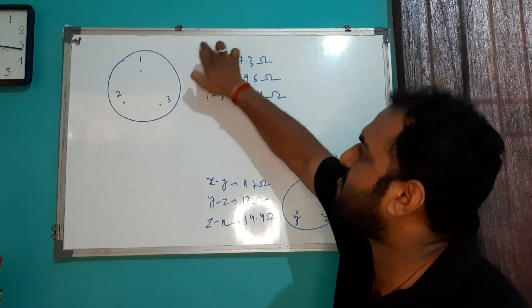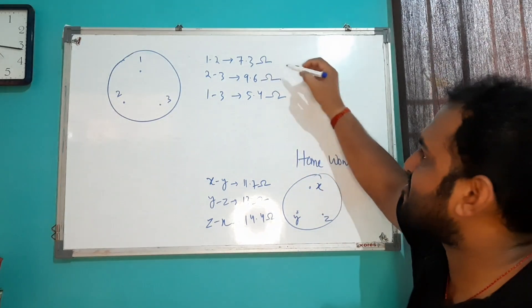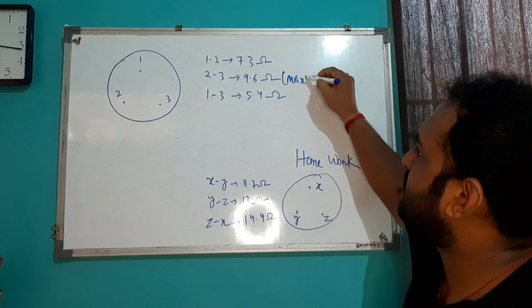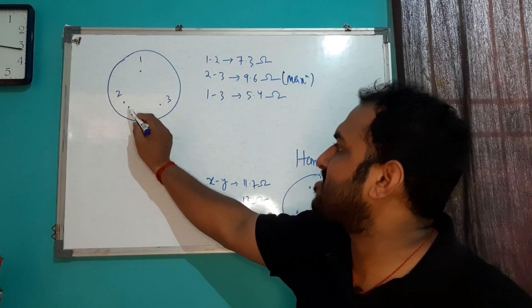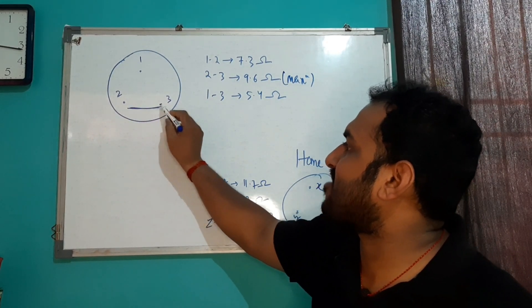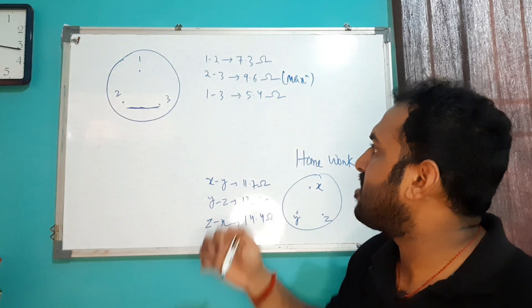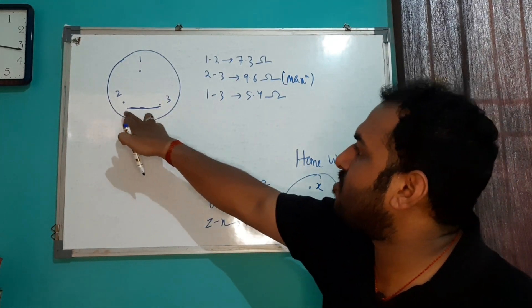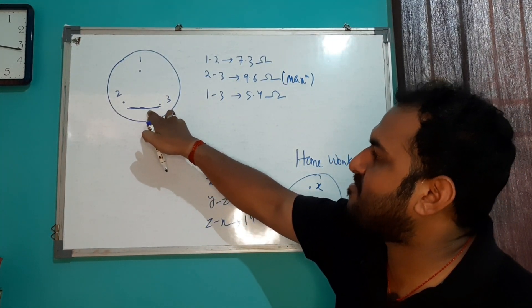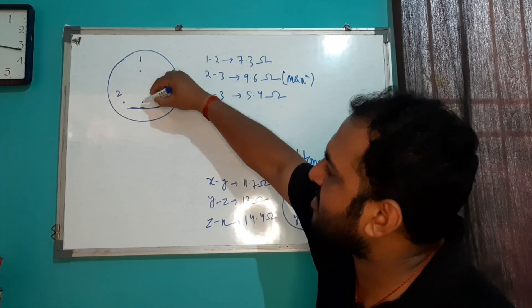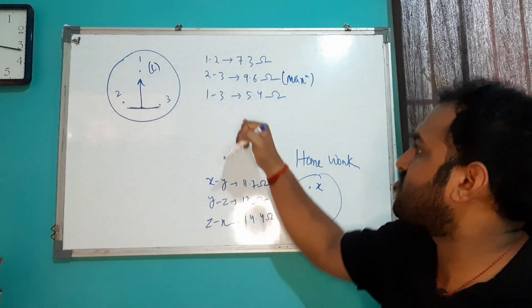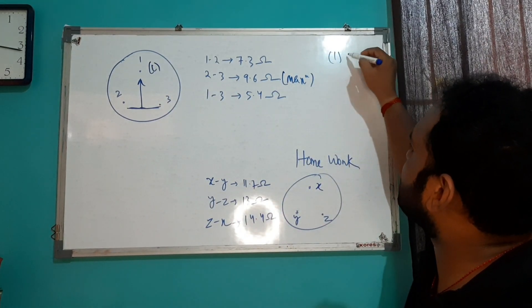The maximum resistance is 9.6 ohms, across the two and three points. So the terminal exactly in front of this maximum resistance pair — that is terminal one — is your C point, your common terminal.